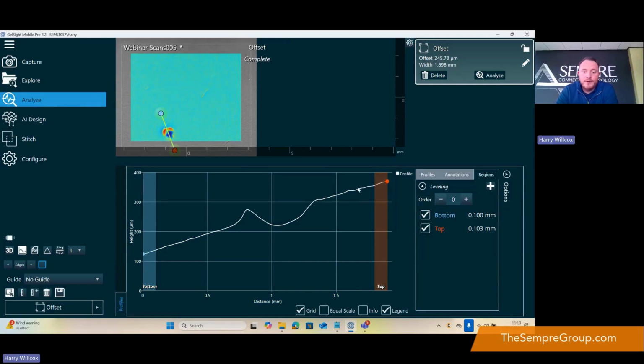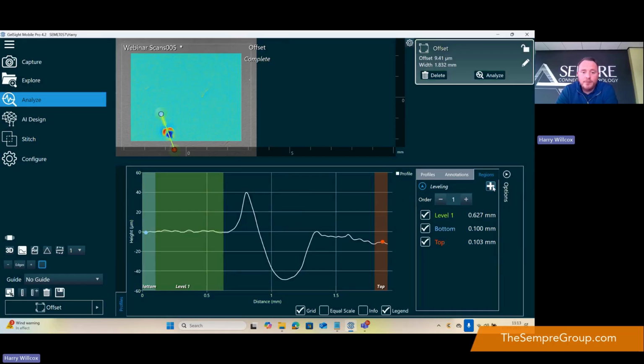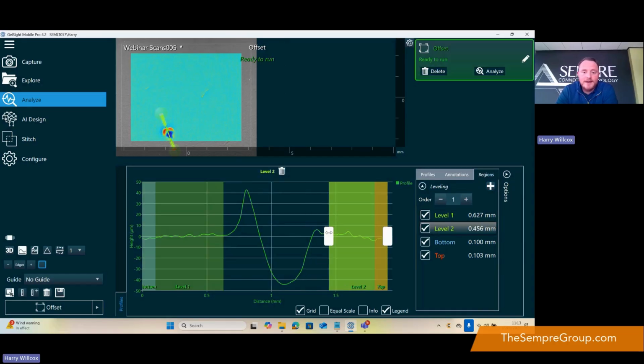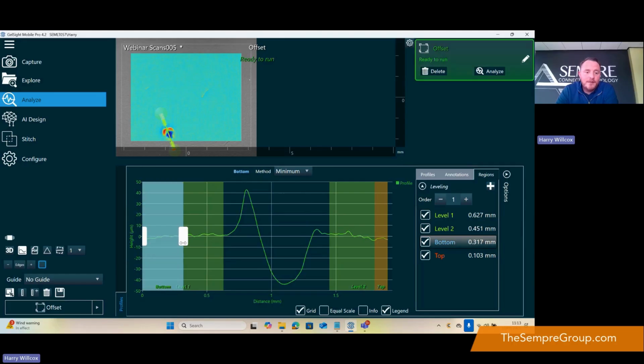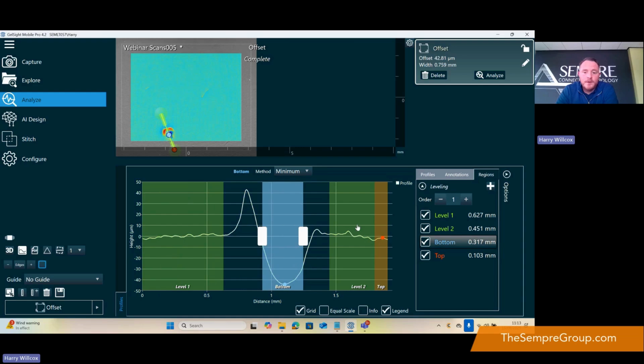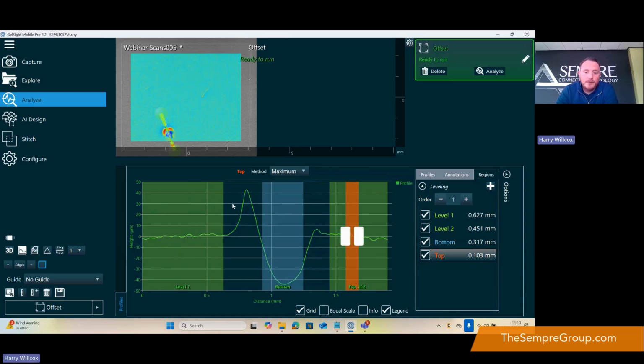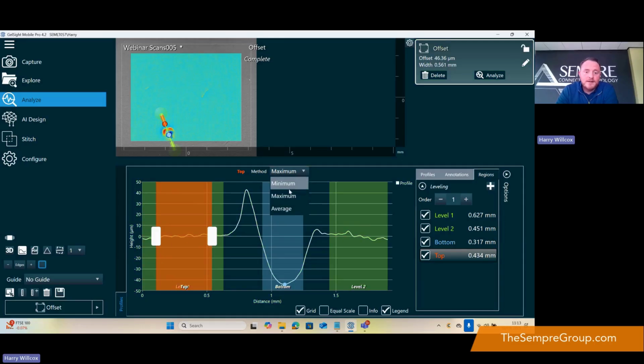And you can see that we've got our defect. Now I'm going to do the same principle again. I'm going to level the data set out. Now I'm able to find the minimum point at the bottom of this channel to the maximum point on the left-hand side. What I'm doing here is effectively asking the system to look for my zero position. You can see on my scale on the left, there is zero. We found the maximum depth of this defect, which is 44.5.